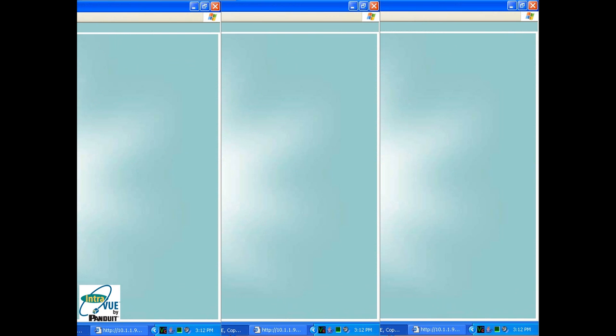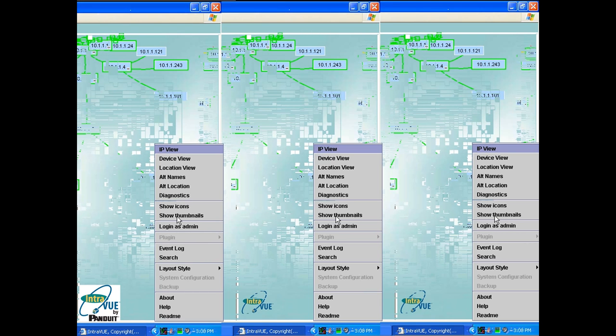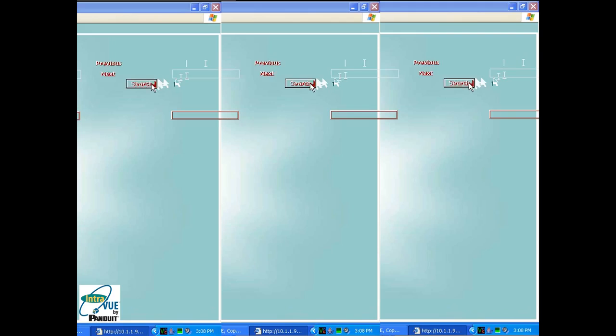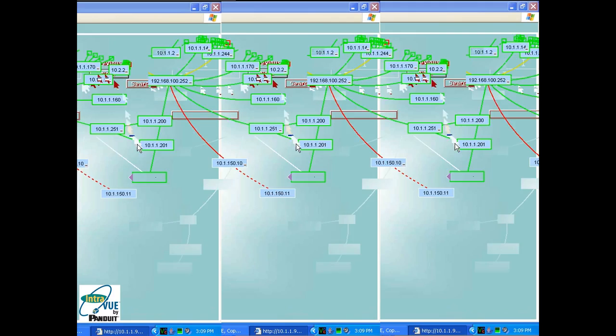If this device had been transmitting multicast messages, for example, implicit messaging of Ethernet IP, and had the same connection problems, you would have seen a dip in transmitted bandwidth, which would have been seen as delays or sluggish data coming from the device, having nothing to do with the application and clearly a connection problem. By viewing the trending dialogues of other connection points, you can identify the potential source of some of these problems.